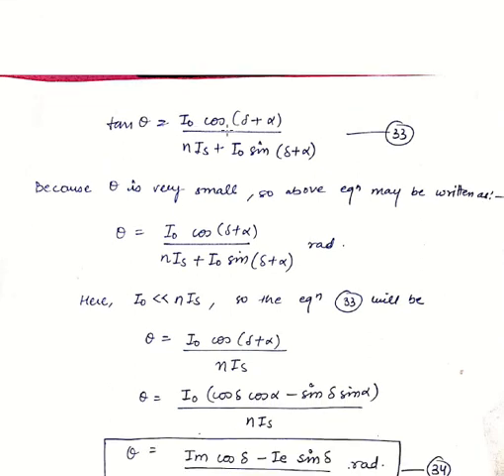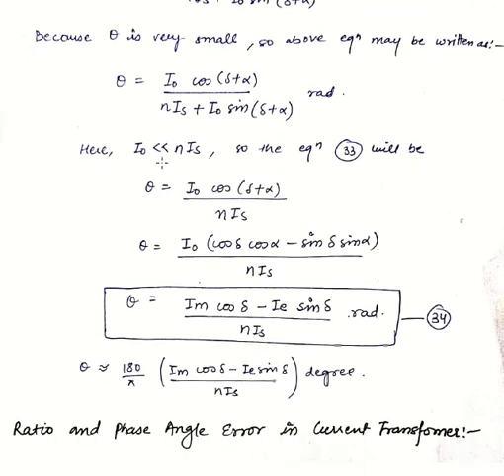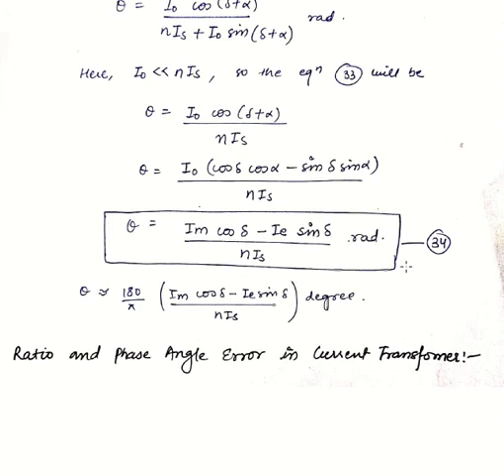When we reverse the secondary current phasor, the phase angle is how much it lags or leads the primary current. The sign is positive if the reversed secondary current leads the primary, and negative otherwise. Deriving the phase angle: if the angle between reversed I_s and I_p is theta, then in triangle OBC we have tan(theta) equals BC divided by OB. Substituting values: tan(theta) equals I0*cos(delta + alpha) divided by (N*I_s + I0*sin(delta + alpha)). Since theta is very small, tan(theta) ≈ theta. Since I0 << N*I_s, the I0 term in the denominator is eliminated, giving theta equals I0*cos(delta + alpha) divided by N*I_s. Expanding: theta equals (I_M*cos(delta) minus I_E*sin(delta)) divided by N*I_s. Converting to degrees, multiply by 180/pi.